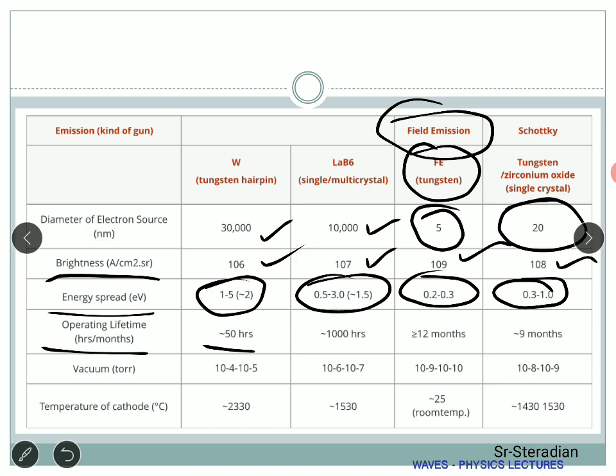Operating lifetime: tungsten hairpin is about 50 hours, lanthanum hexaboride is around 1000 hours, cold field emission is more than 12 months, and Schottky type is more than 9 months. Since no temperature is used in cold field emission, there is no mechanical wear, which accounts for the long lifetime. The vacuum requirements differ: tungsten and LaB6 need around 10⁻⁴ to 10⁻⁵ torr, while field emission requires higher vacuum. The temperature of the cathode is minimum for cold field emission (room temperature), highest for tungsten hairpin, around 1500K range for LaB6, and the Schottky type uses a similar temperature range combined with a field.